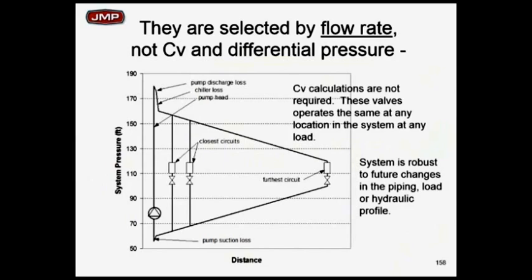And you got to pick the two-way valves. Let's say it's a long campus run. So we got cooling coils, two-way valves in close to the big pump. This is my chill water distribution pump. Pretty high head pump. You see the differential pressure, pretty high differential pressure in close to the chill plant.